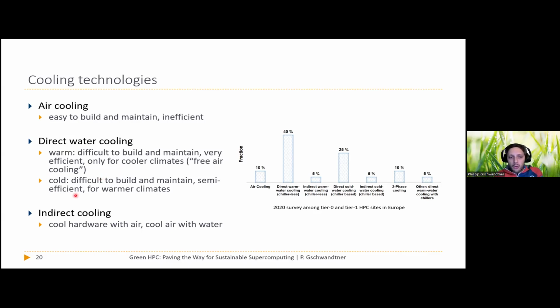Then there's cold water cooling, which does the same, but on the roof you need active chilling — actively cooling the water using the same process as in a fridge, essentially a heat pump to remove heat from the water flow. These systems work well but are less energy efficient, so they're only used in warmer climates where free air cooling doesn't work because ambient temperature reaches 45 degrees, for example.